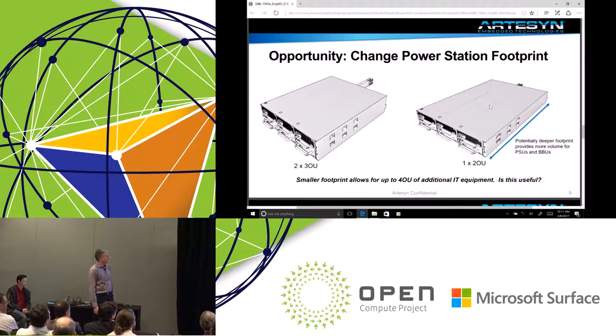Okay. Along with power density, we want to probably use as much rack space as we possibly can for this. So by making a larger power shelf, you can reduce your volumetric density of power, and then you can push up your efficiency along with your capacity within the power shelf. But there are other trade-offs, like this particular shelf. The depth of that shelf was chosen so that there's enough cable bend radius for the shelf. Right? So again, more trade-offs. Next slide.